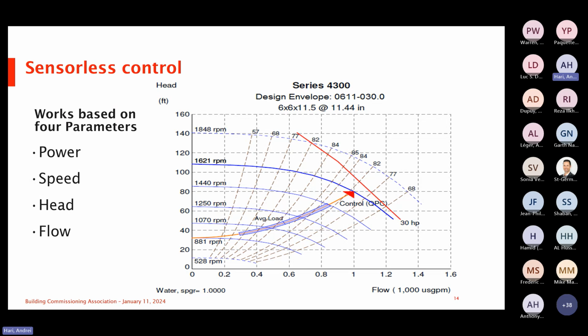When we talk about sensorless control, I'll go back to, first of all, explaining how sensorless control works. As I said in the beginning, every single pump operates based on the affinity laws. There are 5 variables that define a pump's operation: the impeller diameter, the power, the speed, the head, and the flow. If you look at this pump curve right now, we're operating at this duty point right here. We're going to get 1,000 GPM because there's 80 feet of resistance in the system and we're running at around 1,600 RPM.